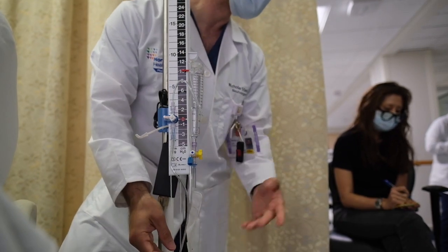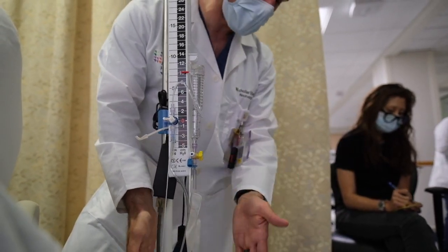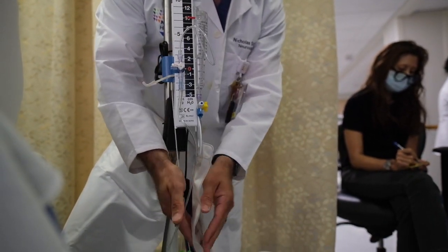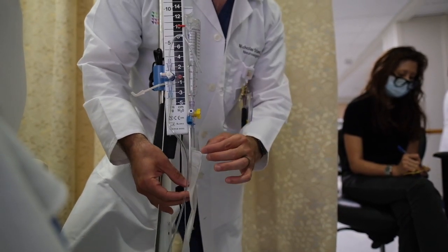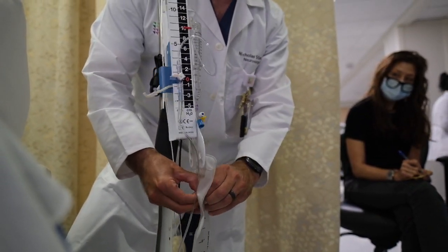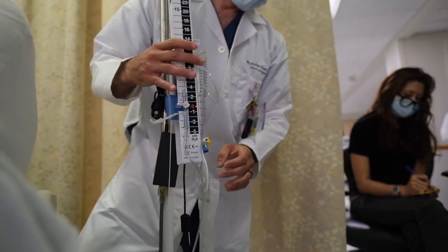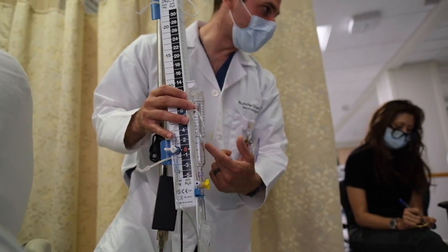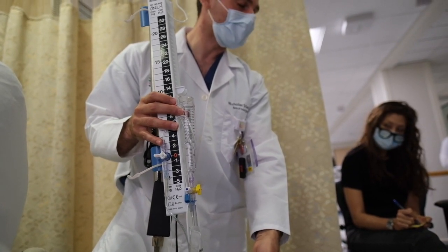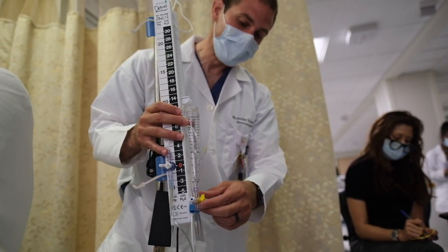Sometimes if you have a fresh system in a fresh bag and this bag is nice and collapsed, it may not drain right away. Sometimes you need to take the two ends of the bag and kind of open them up to allow it to go. So this is only used for when you're emptying the chamber of CSF, okay?